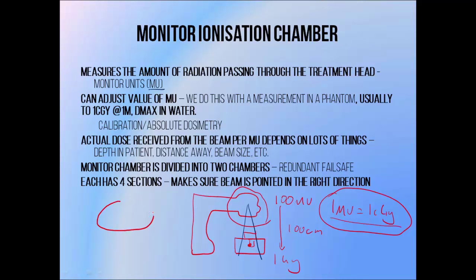The monitor chamber is divided up into two sections, each providing its own independent measure of the amount of radiation passing through the treatment head. This is because if the monitor chamber system broke and stopped recording signal, the beam wouldn't turn off after delivering the required amount of radiation, and we'd keep irradiating the patient with a massively high dose. Having two means that if one breaks, the other will turn the beam off at around about the right time. In practice one chamber does the work most of the time, and another is set to turn the beam off at a dose 10% higher than the primary chamber, so that if something goes wrong there's something there to catch it. Each chamber is also split into four sections, allowing it to determine if the beam is pointed in the right direction.